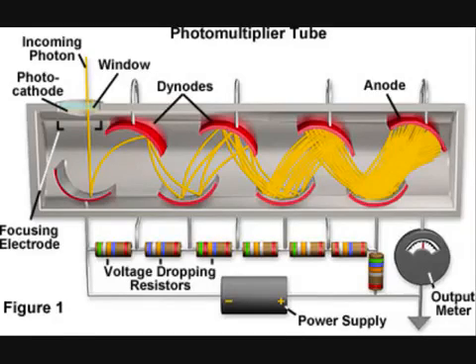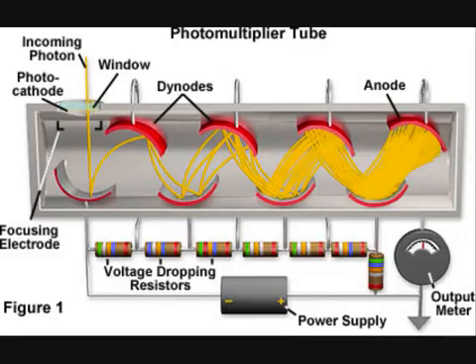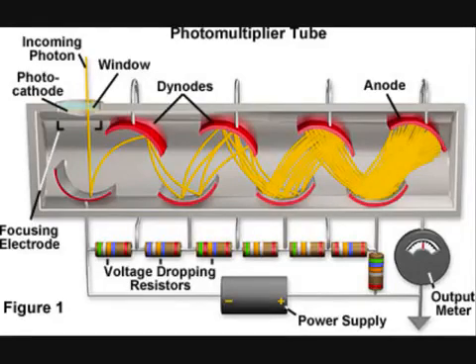Each dynode is coated with a bialkali metal that initiates the photoelectric effect. This process is able to turn a single electron, through a series of interactions with the dynodes, into a million subsequent electrons. Once the electrons have successfully gone through all the dynodes, they are absorbed by the anode and sent to a readout device, creating an electric current.